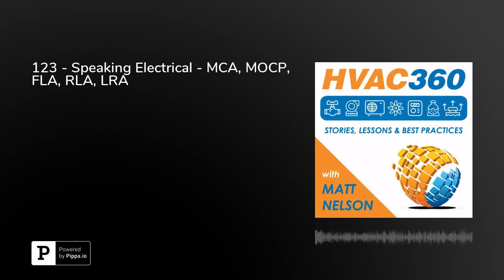But most of the time, you're going to have the MOCP, the overcurrent protection of a device. This is a number that's used to size the circuit breaker or fuse that is usually specified by the manufacturer. Again, you can calculate your own MOCP, but you can also rely on the manufacturer. MOCP will always exceed the MCA. Obviously, you're not going to have a load that's going to be greater than your circuit breaker. So again, MOCP is going to be larger than MCA or the FLA, but you typically don't see an MOCP in a single motor type of configuration. It's mostly for packages. You see that a lot for chillers, things like that. That'll have an MOCP, something that's going to be typically larger. It's going to be more expensive. That's when they're going to give you the MOCP.